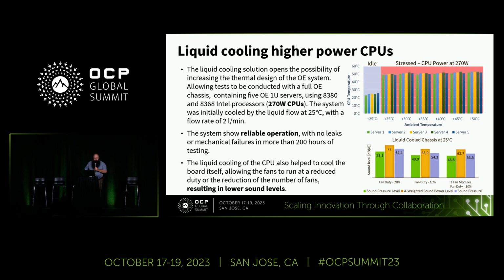Allowing tests to be conducted with a full OE chassis containing up to 5 1U servers, and up to 270 watt CPUs. The system was initially cooled by a liquid flow at 25C with a flow rate of 2 liters a minute, and showed reliable operation with no leaks.